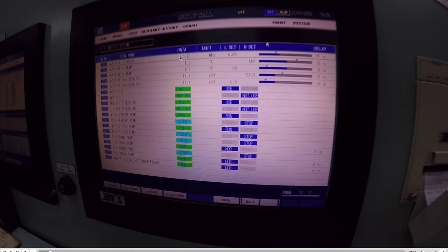And also this pressure, it's really, really important to check during your duty or during the morning time when you're going to the engine room, because there are some filters that need to be cleaned. And most of the problems that you can have from the filters can be also the pump seals, because as you know, if the pump suction is too negative, the pump will be pressed excessively, so all the equipment will be overloaded, all the shaft, all the motor, the bearing. That's why it's really, really important to clean the filters.